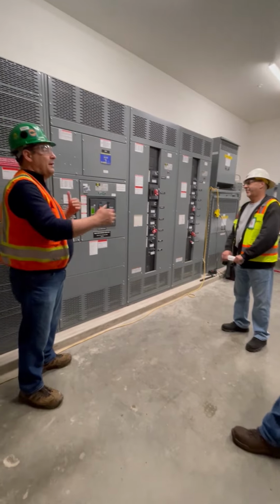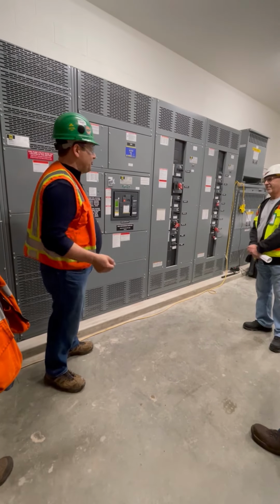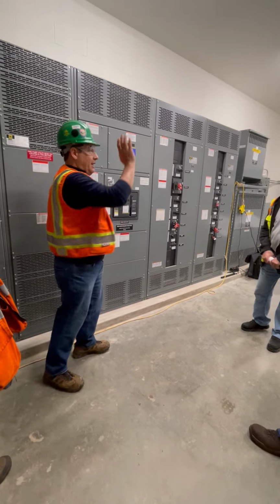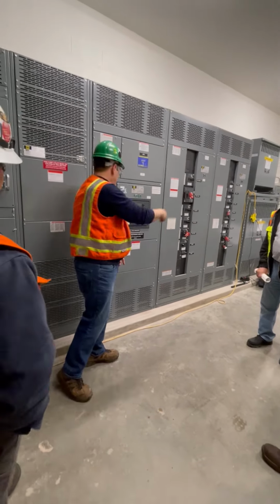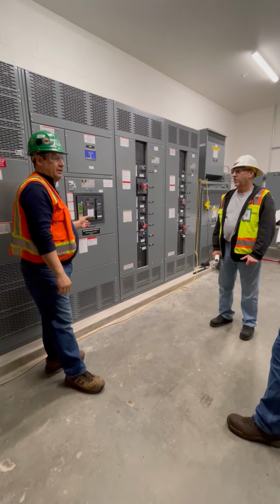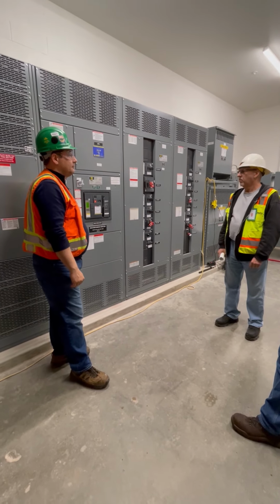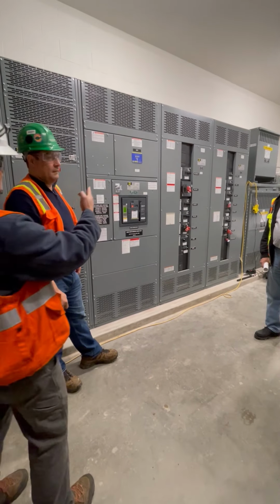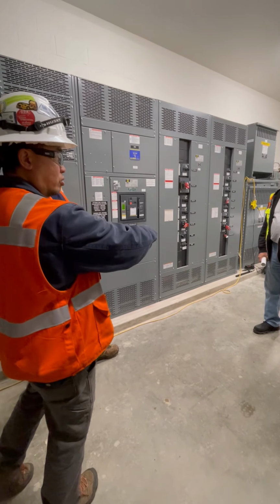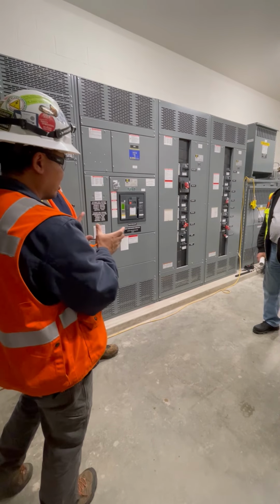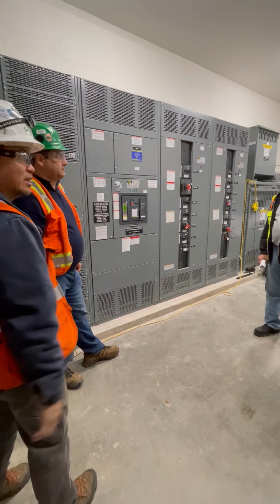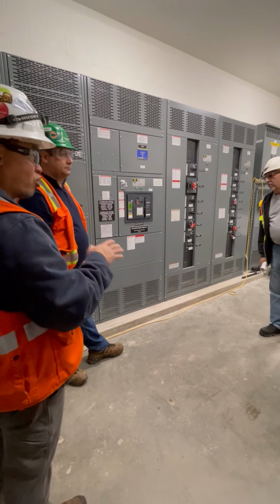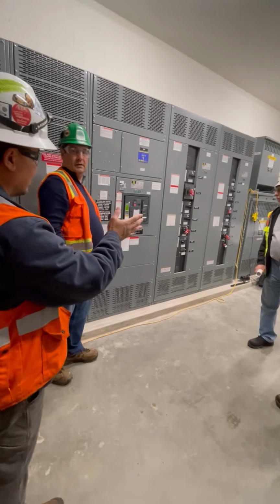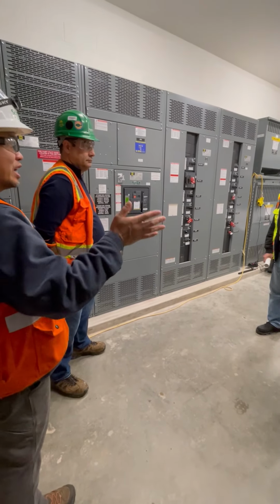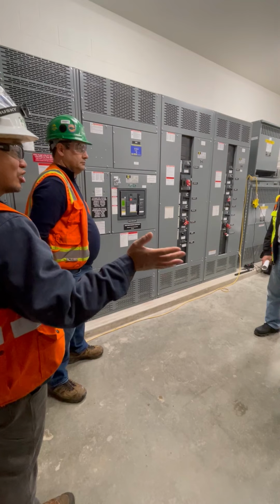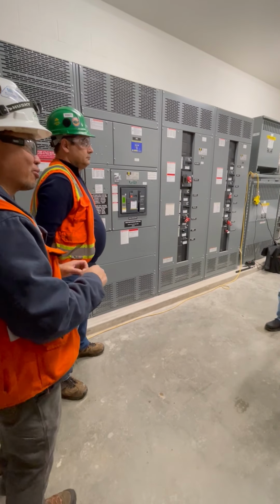I'm probably overkilling it by saying a cord or something, but you could have an issue at a panel, who knows where down there. And when it comes to ground fault, this is the only place that may take place. A hospital requires two levels of ground fault, so your main and all the feeders in the switchboard. So if there's a fault downstream, the feeder would trip, so you coordinate that. That's the NEC code requirement for hospitals, but it's not required for a school or anybody else, only for critical facilities. That way in the hospital it won't lose everything, like with someone on the operating room table.